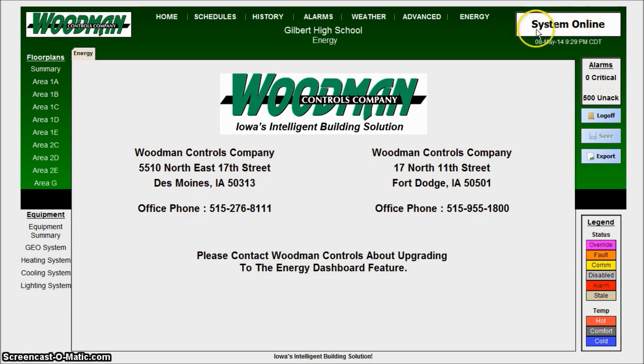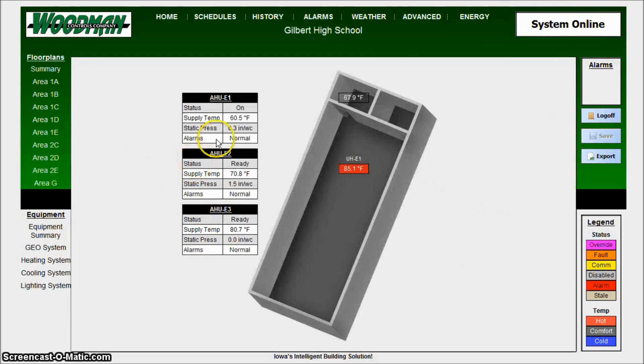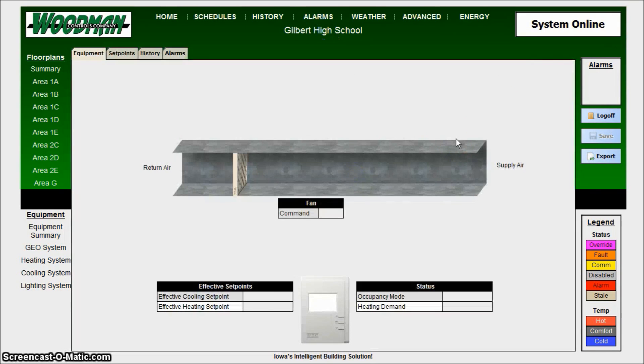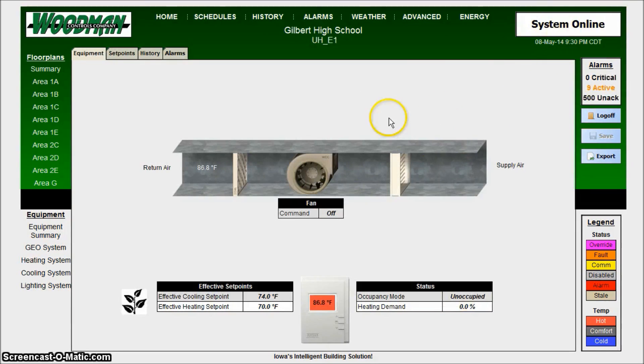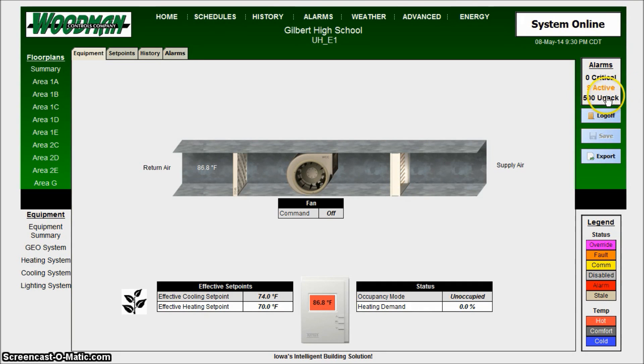The System Online indicator shows the status of whatever piece of equipment you're currently looking at. Right now it's showing the building is online, but if you navigate to a particular room, it shows that specific controller is online. If something is off, you'll see it turn yellow and possibly flash red — for example, in the case of a fire alarm. For alarms, there are a few active non-critical alarms here, but no critical alarms in the building. This customer doesn't acknowledge their alarms very often, which is why there are no acknowledged alarms shown.